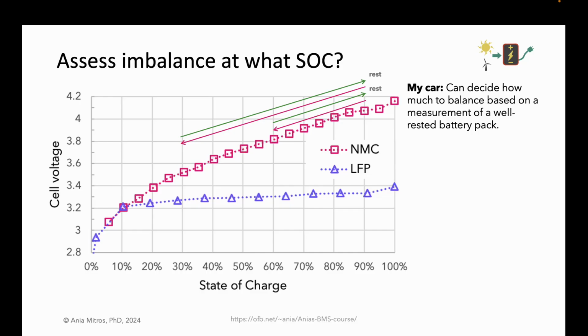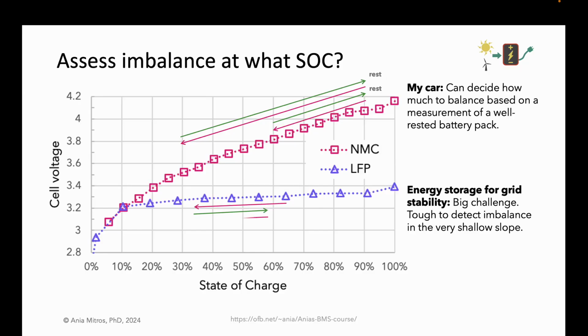Since the slope of the voltage versus SOC curve is moderately steep for the NCA cells or NMC cells in my car, where on the curve we take the measurement is not very consequential. Recall that a given measurement error, say 5 millivolts, will have a larger impact on the SOC estimate when the slope is flat than when the slope is steep. An energy storage battery used for grid stability, on the other hand, is intentionally operated around 50%. Oftentimes, LFP cells make most sense for stationary storage, where their advantages of better safety and better cycle life outweigh the disadvantage of slightly lower energy density. A battery can operate for many cycles in that very shallow middle part of the curve, where estimating SOC from voltage is very difficult. In this scenario, the pack can become unbalanced, and the voltage difference may be too small to detect in the application.